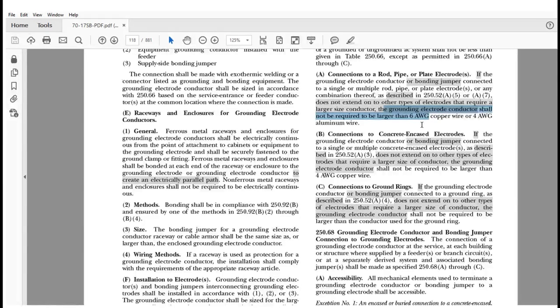So, very clear now what it meant to say before. I applaud Code Making Panel 5 for finally getting rid of the term sole connection and clarifying, saying, hey, we don't care if you go to an electrode of the same type with the size that's required. But at any point you change from, let's say, these three here, you go to a ground rod, and you want to then jump from a ground rod to some other type of electrode that's going to require a larger conductor, you can't do that. The whole integrity of the actual path itself has to be established with the larger conductor.